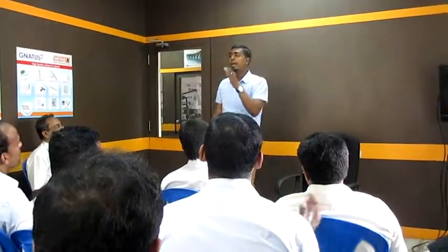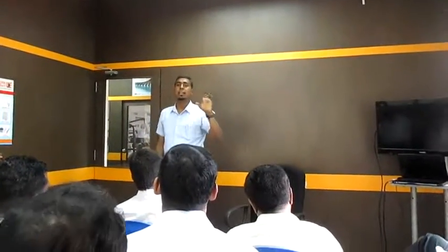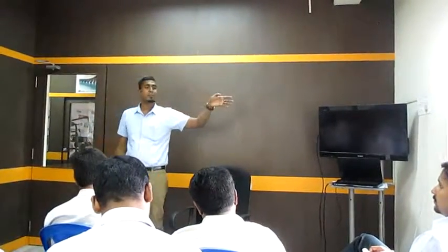The filter which we add to the machine, to the tube, is added, and the filtration which the X-ray machine itself has inbuilt is inherent. The sum of inherent plus added is its total filtration. Okay, and now, what is the role of filtration? Who will tell me what is the role of filtration?